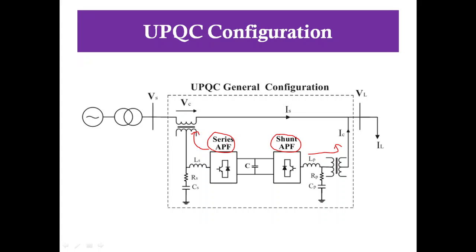The Series Active Power Filter is used to mitigate the voltage disturbance and harmonics in the power system by injecting voltage. The Shunt Active Filter is used to compensate the reactive power in the power system by injecting current. The Shunt Active Filter is also used to regulate the DC link voltage for both filters. This is the main operation of UPQC.